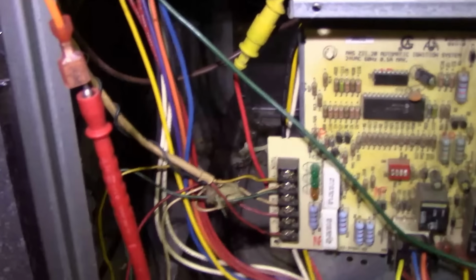If we go in the blower compartment, yes, the life of an HVAC technician gets interesting with the things we see. Yes, this is fairly dirty. Looks like this furnace might have a somewhat new motor on there. Nobody taped over the capacitor, which is good. Also with these Molex plugs right here, sometimes on these particular models of Rheem furnaces, it goes straight through and gets right there. They tend to get a little dirty, which gives bad wire connections, all that stuff, and it can cause the furnace to act up.